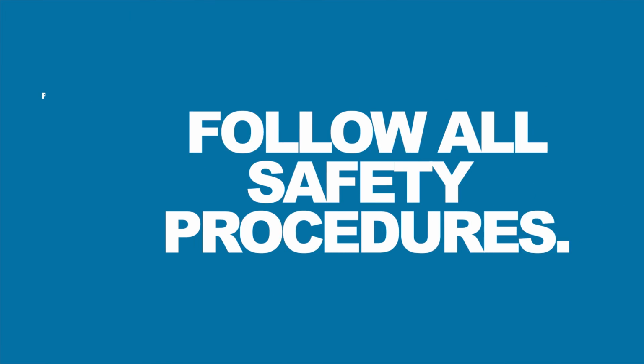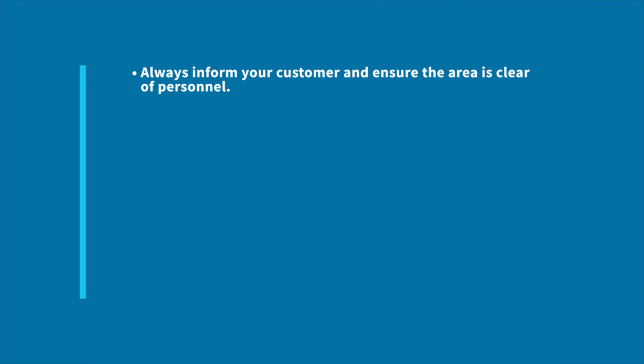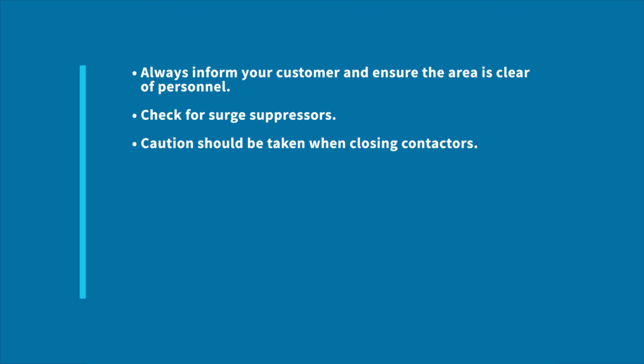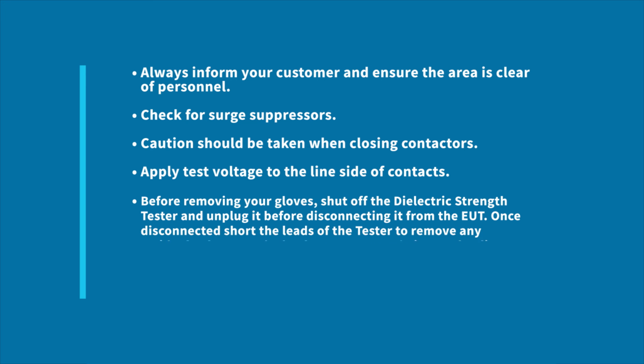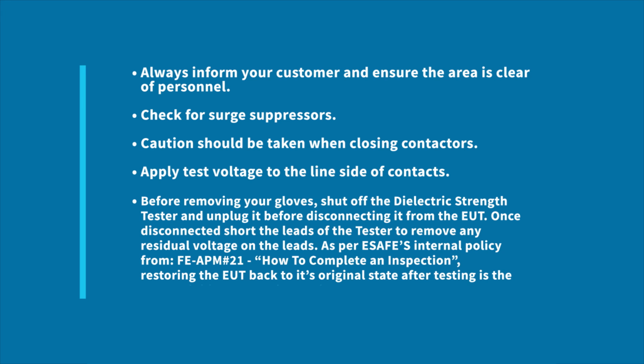Follow all safety procedures. Always inform your customer and ensure the area is clear of personnel. Check for surge suppressors. Caution should be taken when closing contactors. Apply test voltage to the line side of contacts. Before removing your gloves, shut off the dielectric strength tester and unplug it before disconnecting it from the EUT. Once disconnected, short the leads of the tester to remove any residual voltage on the leads.